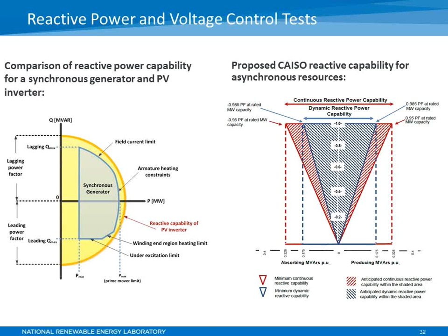The proposed reactive power capability characteristic, which is shown on the right, is one California ISO actually proposed for asynchronous generation. It defines the requirements for dynamic and continuous reactive power performance by variable resources, and we used this as a guideline and tested the plant's ability to comply with this particular response. So the plant's ability to provide reactive power control and voltage control was tested at two different power levels. The XY graph shown on the left here shows the measurements compared to the proposed California ISO reactive power requirement.